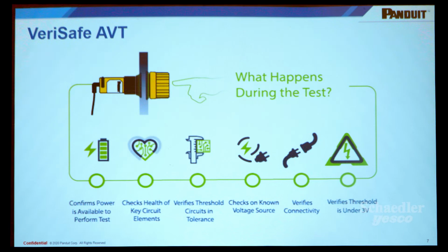In order for UL to approve this and for NFPA 70E to adopt it, we had to make it a smart system. Basically, the AVT system has to do a full self-diagnostic test twice. So it checks to make sure that it has enough power to complete the job. It checks all the circuitry to make sure it's working correctly. It calibrates itself every time and checks its calibration. It then does the electrical test, and then it redoes all those tests one more time to make sure that it's working correctly.